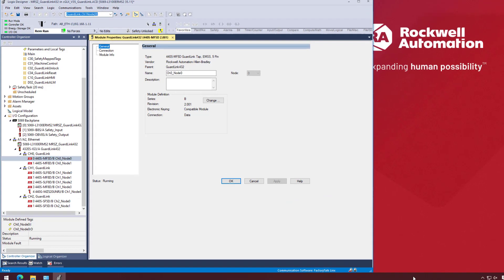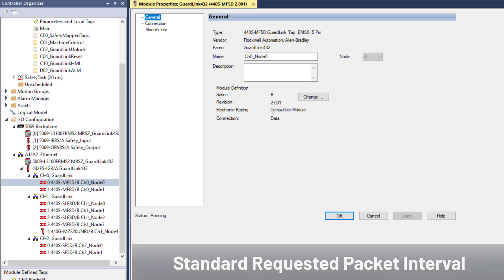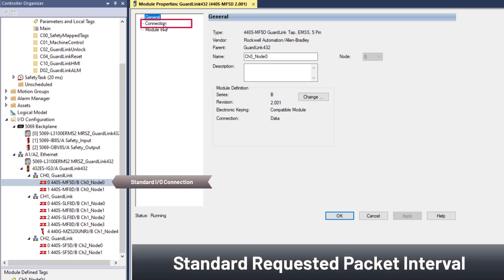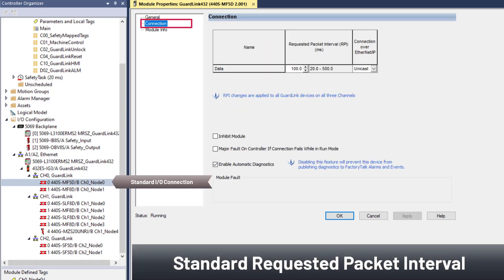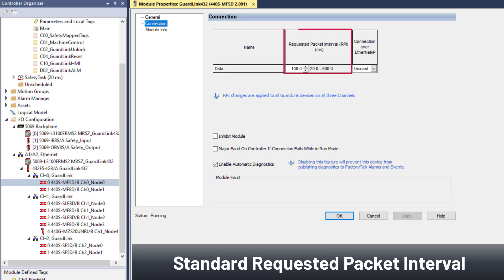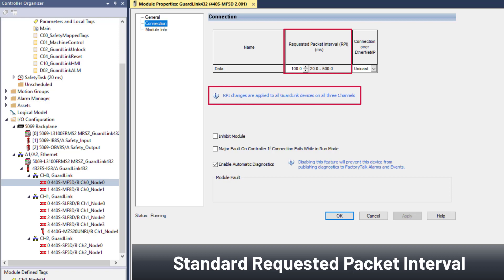Before moving to the standard logic, let's review the standard node communication requested packet interval. Information from the GuardLink nodes is handled by a standard input-output connection. The requested packet interval for every node on every channel of a GuardLink interface module is the same. Since this information is not safety critical, the application was left at the 100 millisecond default setting.